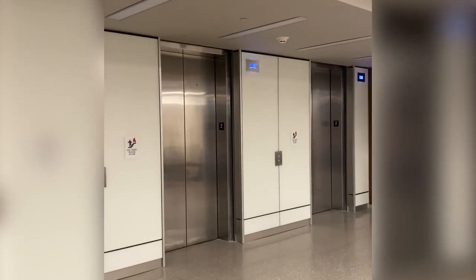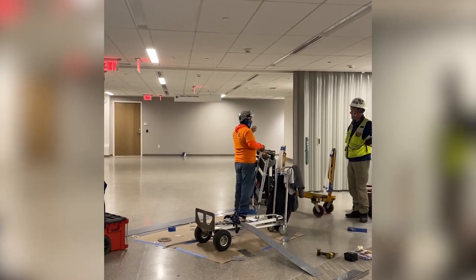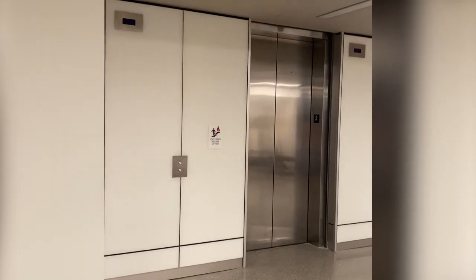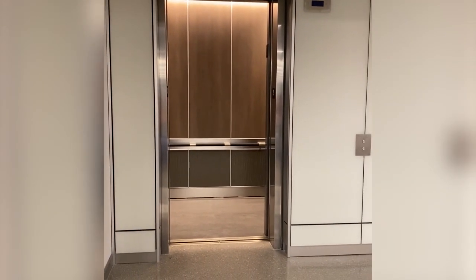As part of that test, we also tested elevators — initiated the fire alarm and tested the elevator recall to make sure the elevators came down to the floor they were supposed to, racing against the fire curtain closing off the elevator lobby. We're on emergency power, in fire alarm, making sure the elevators work — and ta-da, the elevator door opened. Successful test.